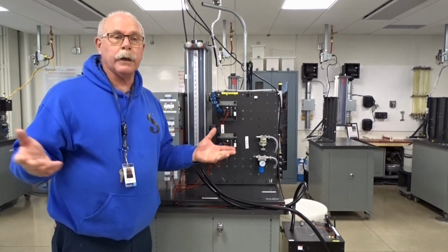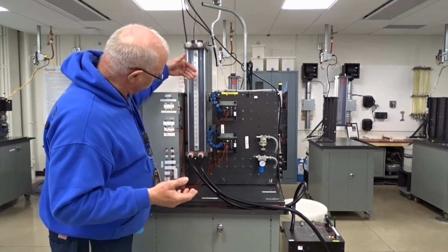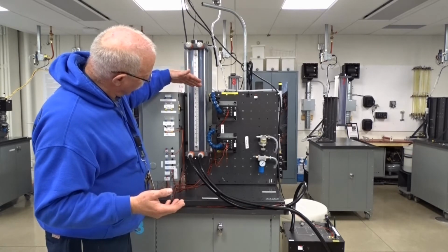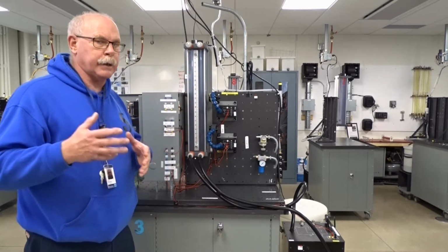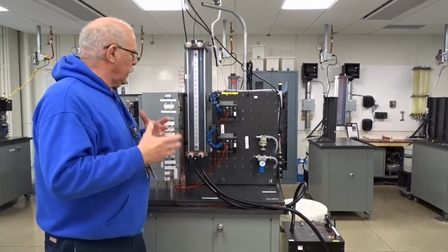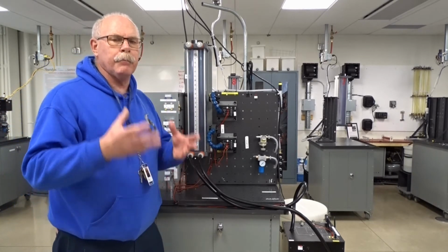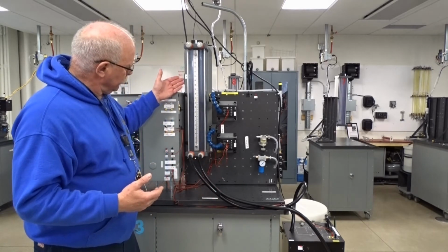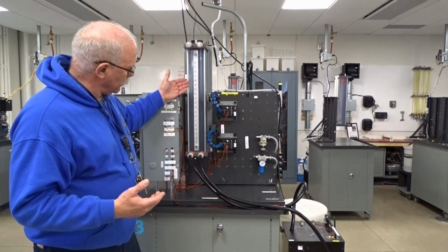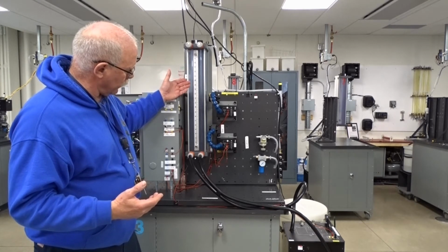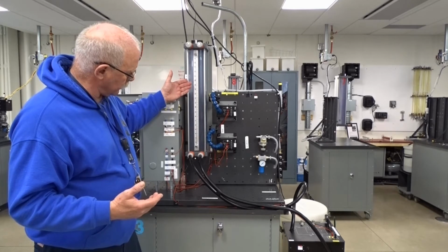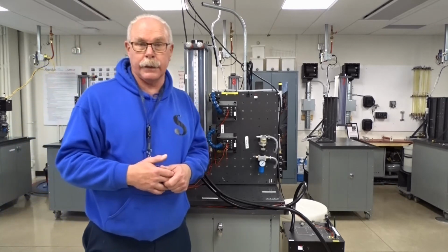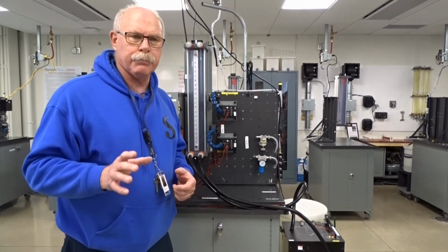Now, if we look at what happens here, the water level fills up, the pump shuts off, but the water level drops. So what we actually have here is some dead time. The process variable has changed, but there is no action by the controller. Now, if I count out 1001, 1002, 1003, 1004, 1005, 1006, 1007, 1008, 1009, about 9 seconds of dead time.